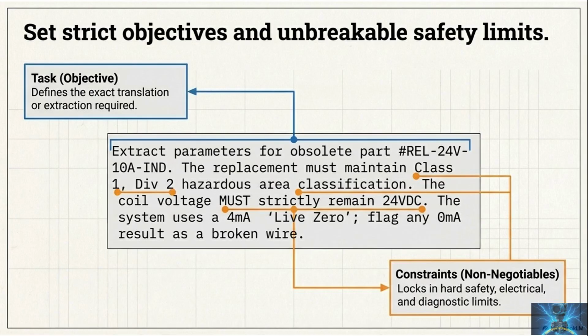Set strict objectives and unbreakable safety limits. Now define the task and the constraints. Task means exactly what you need, extracted or translated, nothing vague. Constraints lock in hard limits, safety classification, voltages, diagnostics rules, and must not change requirements. This example calls out Class 1 Division 2, so the replacement must keep hazardous area compliance. The coil voltage must remain 24 volts direct current, no close enough. The live zero rule is also a constraint. 4 milliamps is a valid active signal, and 0 milliamps is a broken wire until proven otherwise.